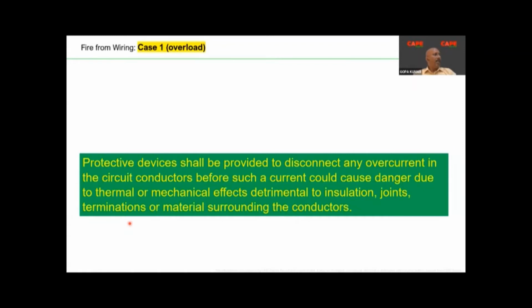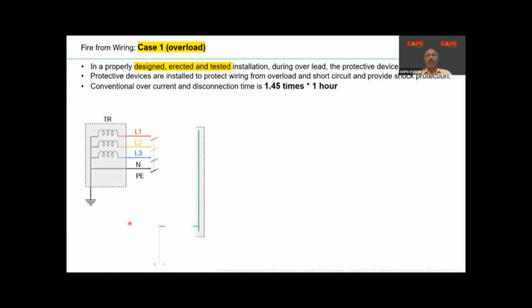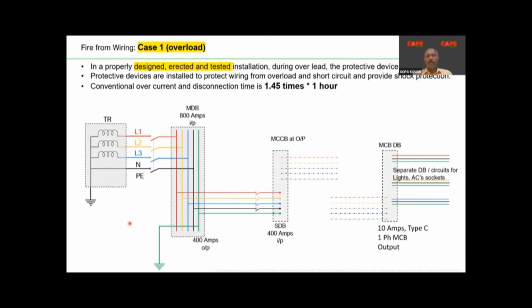The first idea of electrical safety is that the protective devices shall be selected, designed and installed in such a way that in case of any trouble, any overload, overcurrent or short circuit, the device is supposed to disconnect so that there is no problem in the installation. The first one is overload. People always say that the fire is due to overload, because the hospital is designed for 10 beds or 10 operation theaters, and then finally 24 hours instead of 10, 15 numbers are running. As a result, overload happened and fire has happened. This is absolutely not possible, because in your wiring, in case of any overload, your devices are supposed to trip. Your devices should trip so that you cannot overload.